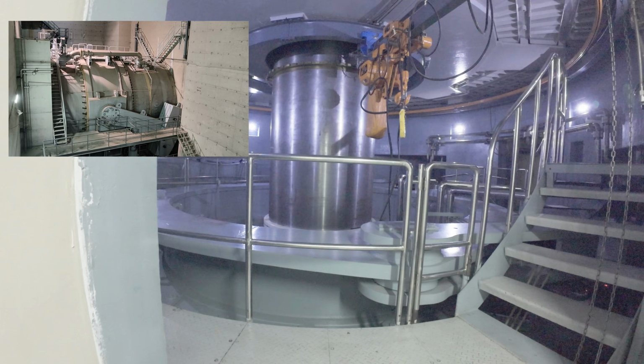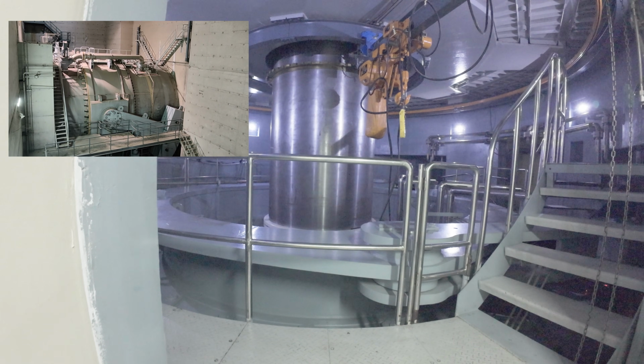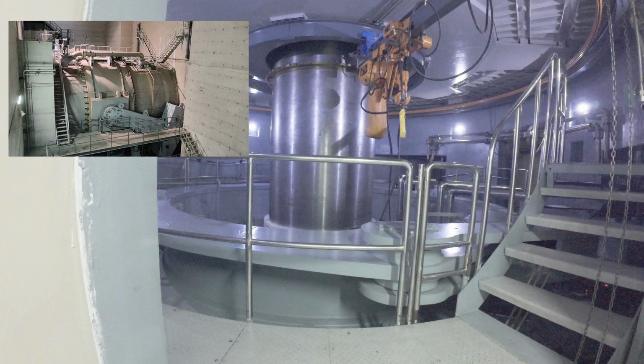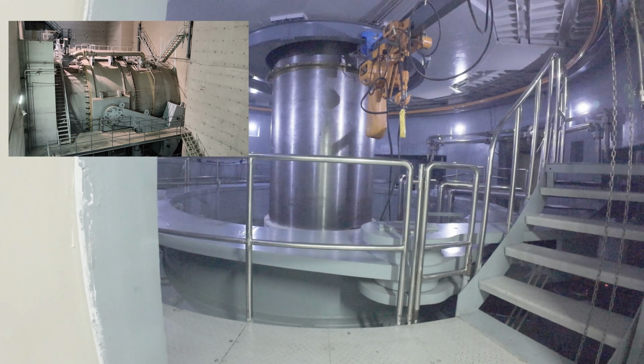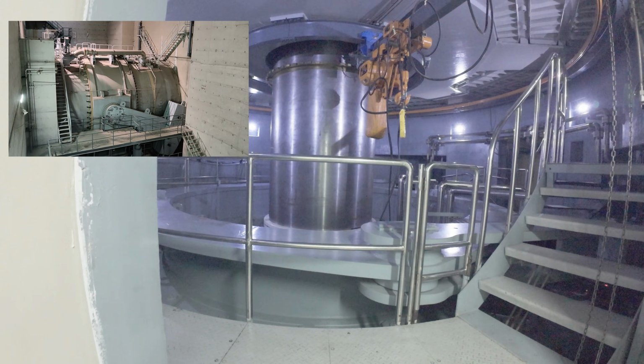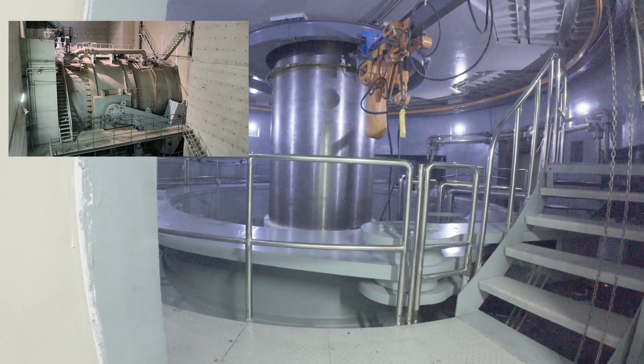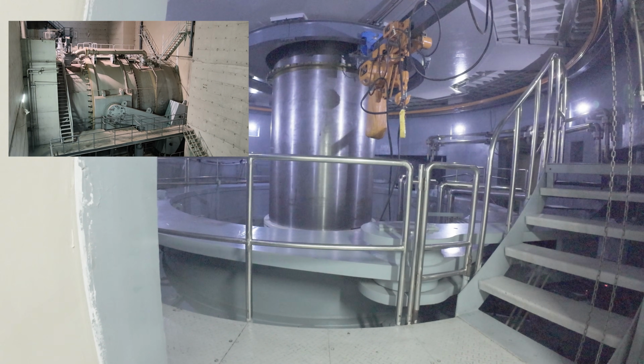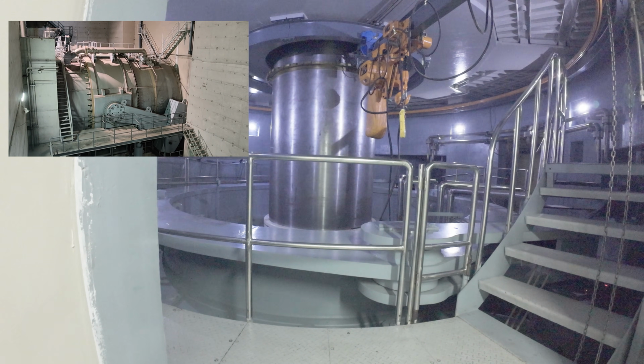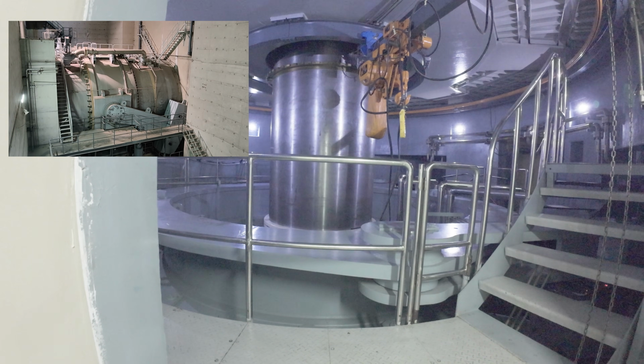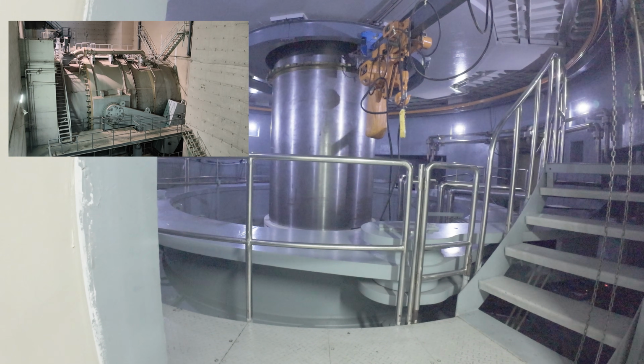Behind this valve is an enormous amount of water under pressure waiting to flow towards the turbine. But many viewers keep asking about these large weights attached to the main inlet valve. What are they for? The answer is simple. These weights are part of a safety system. As long as everything is working normally, the valve stays open. But if electrical power is lost, hydraulic pressure disappears, or the control system fails, gravity takes over. The weight helps move the valve towards a safe position automatically. No electricity, no computers, no batteries, just gravity doing its job. It is one of the simplest and most reliable safety systems in the entire power plant.